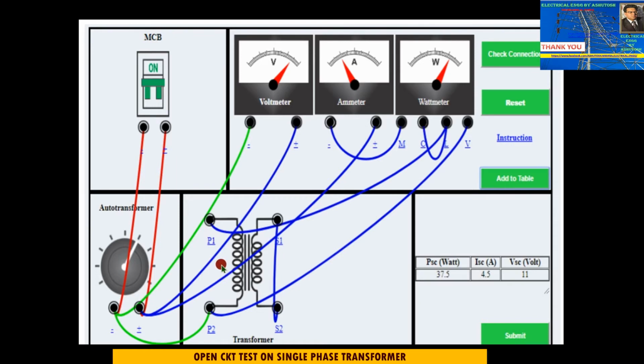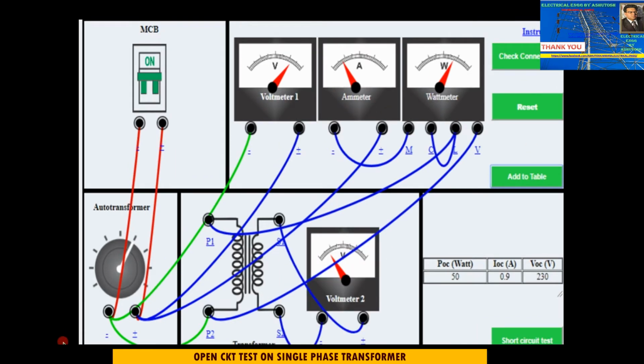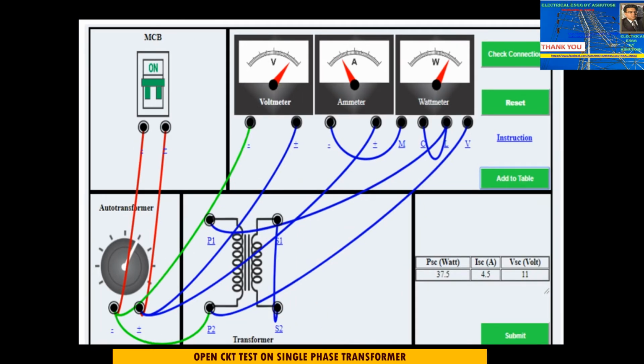Okay, but here during this open circuit test, the primary is low voltage winding, and secondary is high voltage winding. Generally the test is conducted at the low voltage winding during open circuit test, and the high voltage winding, the secondary, is kept open circuited. For short circuit test, the primary winding is high voltage winding, and the secondary winding is kept short circuited, and that is always low voltage winding.